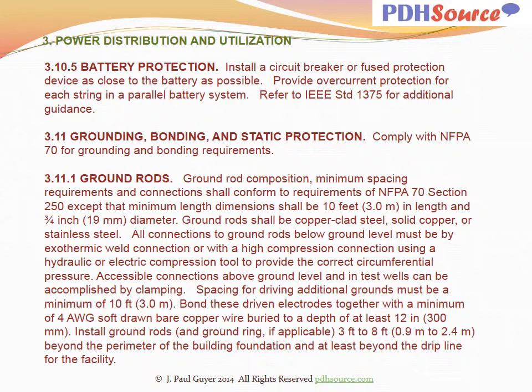Install a circuit breaker or fused protection device as close to the battery as possible. Provide overcurrent protection for each string in a parallel battery system. Refer to IEEE standard 1375 for additional guidance. For grounding, bonding, and static protection, comply with NFPA 70.